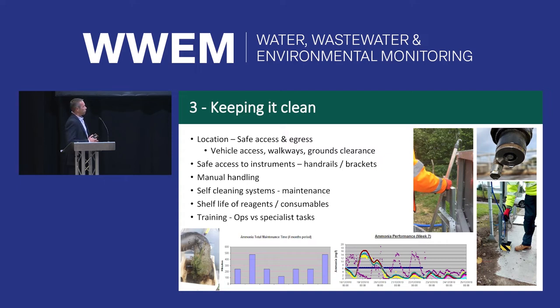But for all of them, a lot of these analyzers are fairly complex pieces of kit, or the sondes take specialist knowledge to maintain. So we also try to reduce the burden on our more skilled technicians by having some operations tasks in there as well - to keep the filters clean, get the instrument out, check the cleaning systems are working properly.